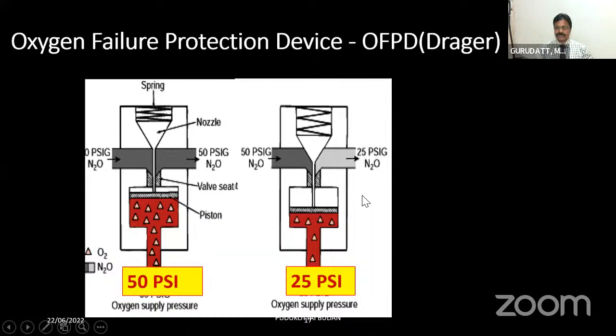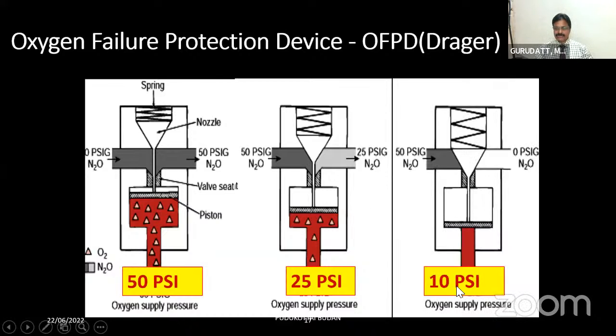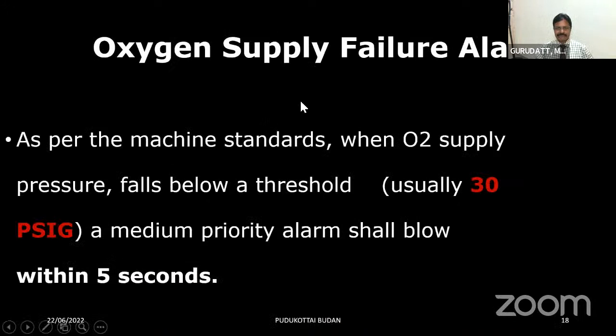So once the oxygen pressure drops, and if the oxygen pressure drops down to 10 or less than 10 psig, this nozzle comes completely down and totally obstructs the flow. That means the flow completely shuts off at 10 psig in OFPD, that is oxygen failure protection device. That's a slight difference in the oxygen fail-safe valves between GE machines and the Draeger machines you should always be knowing about. Coming to the oxygen supply failure alarm, another component of the intermediate pressure system.